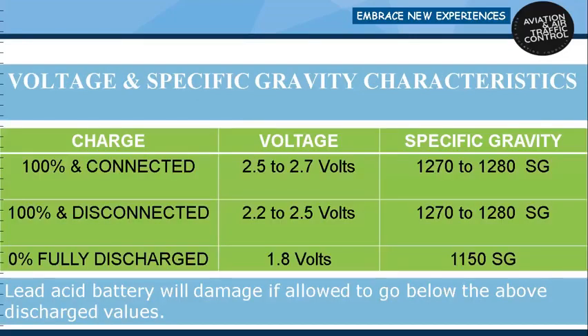The voltage and specific gravity figures for a lead acid battery: when 100% fully charged and still connected to the charging board, it will show 2.5 to 2.7 volts and specific gravity of 1270 to 1280. When 100% fully charged and off charge, it will show 2.2 to 2.5 volts with specific gravity of 1270 to 1280. When fully discharged at 0%, specific gravity will be 1150. The battery will be damaged if allowed to go below the above discharge values.